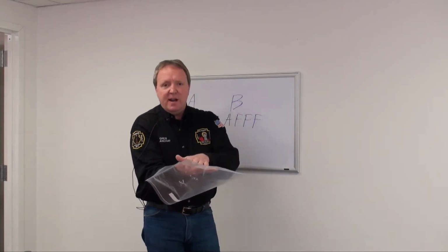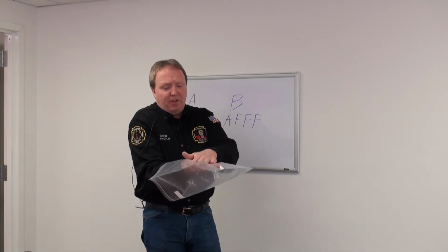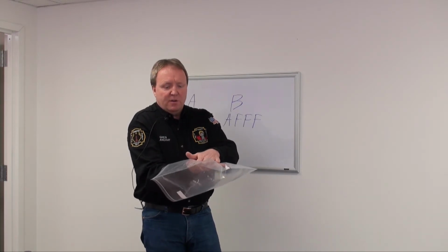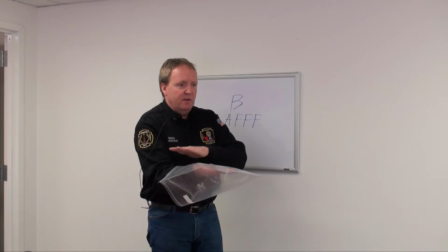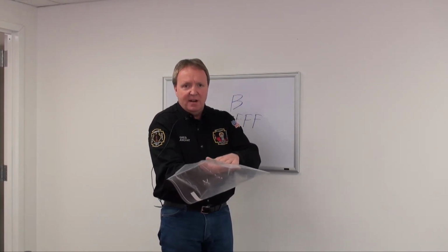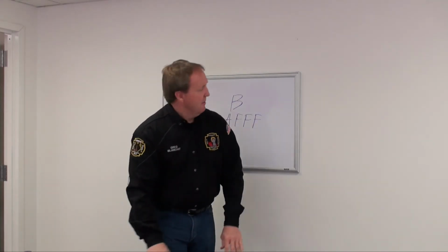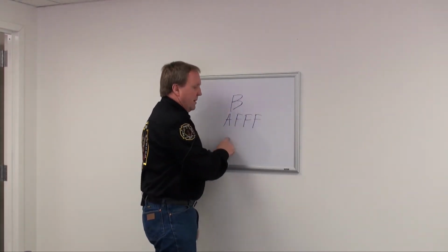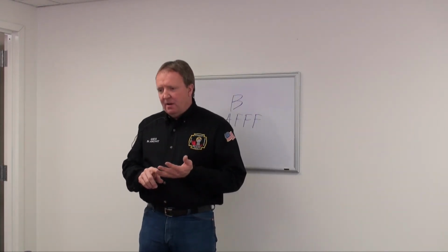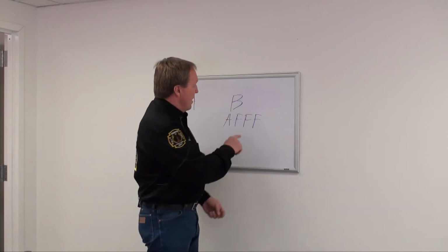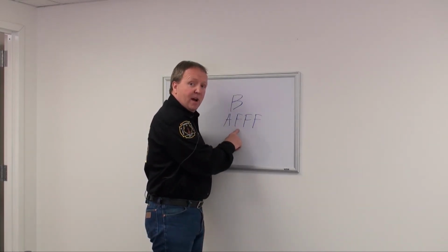A lot of times you can't even see this real thin membrane of foam. So you're separating. That's the reason you don't want to walk on a treated area, because you can break this skin of foam. You've got a lot of different B foams, and a lot of these B foams that are coming out now are alcohol resistant, to help put out an alcohol fire. Don't make a mistake, alcohol will break down this foam in a period of time.